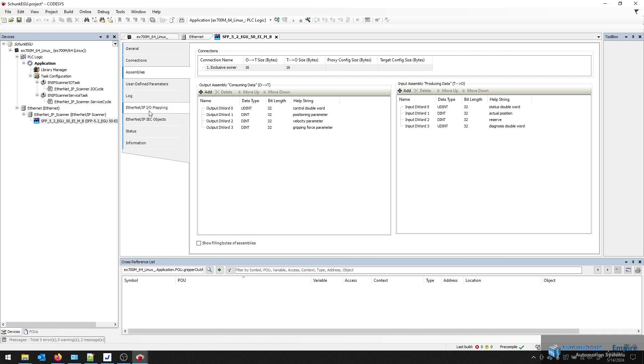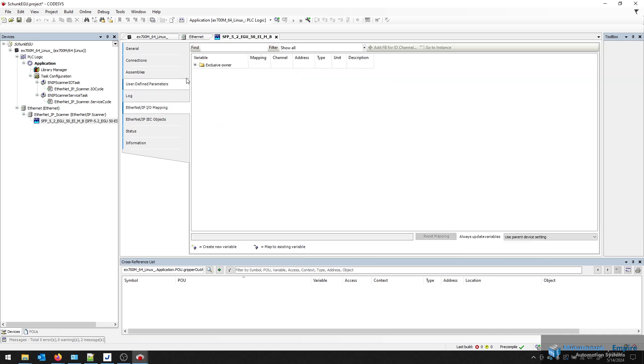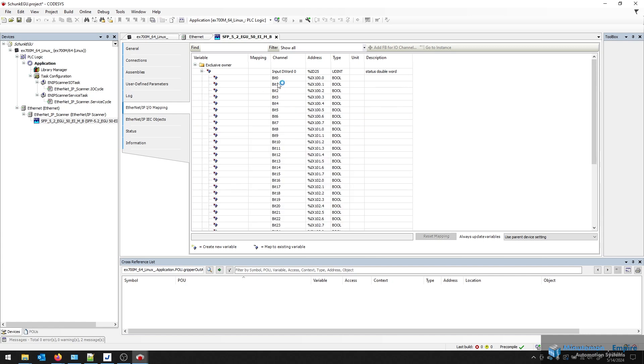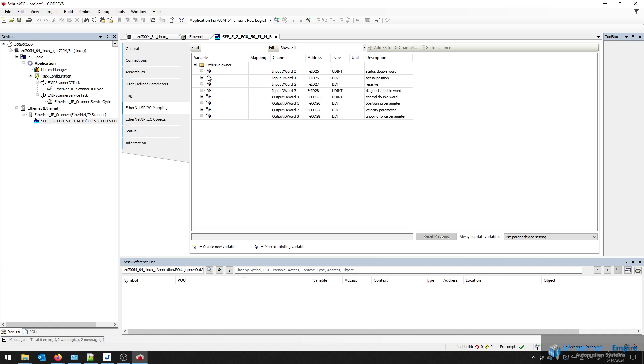And if I go down to my IO mapping, I'm able to actually start mapping my tags to my respective bits. Some of these are going to be DINT for the larger values, such as positioning and velocity. So please make sure you have the appropriate size tag for that location. I'm going to jump ahead to a different project that is already completed.